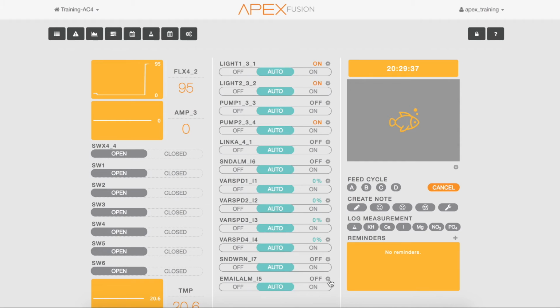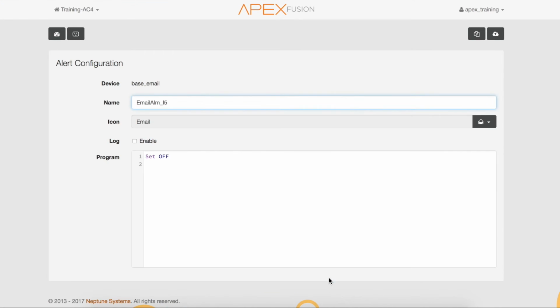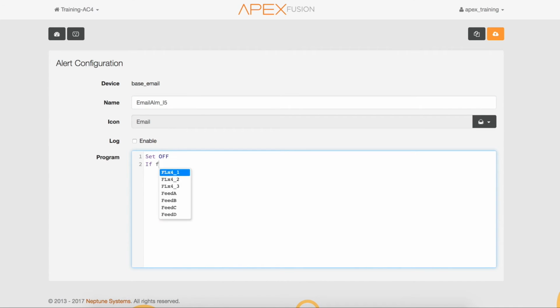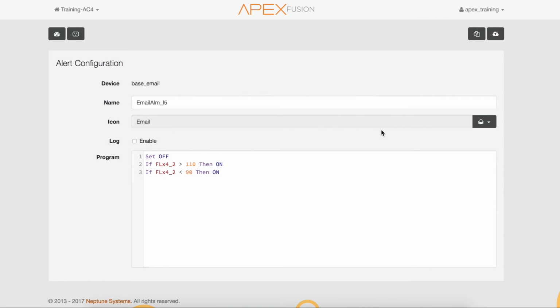To set up an email alarm for your flow sensors, click on the gear icon next to the email outlet on the dashboard. When programming outlets in Fusion, there is an advanced editor that will help you autofill your programming. All you need to do is type in the first letter of the command and it will show you all valid programming. The programming that I am doing here says if the flow sensor on port 2 of the FMM on address 4 detects a flow greater than 110, then turn on the email alarm, or if that same flow sensor has less than 90 gallons per hour going through it, turn on the email alarm. Once I have programmed the email alarm, I select Save and then OK, and it has been configured.